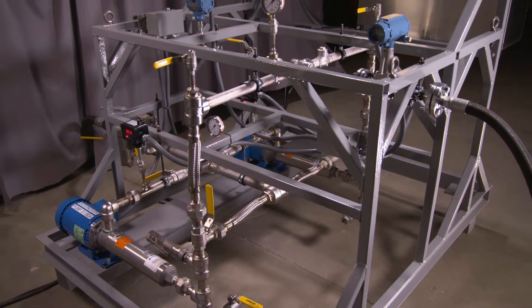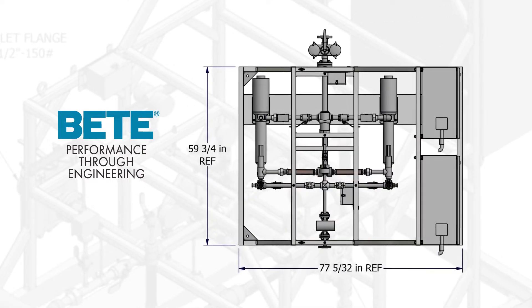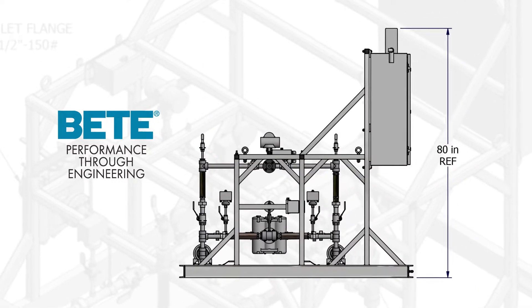To protect downstream pollution control equipment, this customer asked BETE to provide a water injection system to cool hot exhaust gases from 1200 down to 350 degrees Fahrenheit, with the added requirement that water had to be completely evaporated prior to reaching the end of the duct.